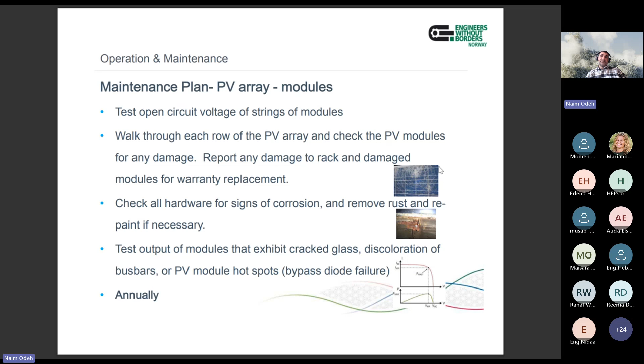Now, the good thing about recent inverters is you don't need to do open circuit testing at site one by one, though visual inspection for cracks and damages is still important. Before, it was recommended to disconnect strings and test them. Now most recent inverters have string monitoring, so you can check the VOC, the short circuit current of the string, and so on directly from the inverter. Most inverters also support remote monitoring - most manufacturers now have an application where you can monitor your system wherever you are, and you even get an alarm if there's an issue with any of the strings. So things become easier, but it's important to know the fundamentals.